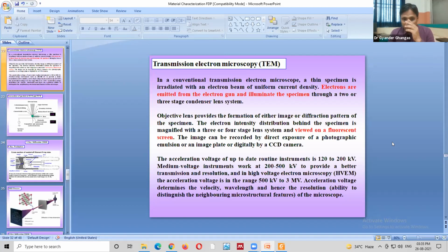So the acceleration voltage of a routine instrument up to date is 120 to 200 kilovolt, and medium range 200 to 500 kilovolt, to provide better transmission and resolution. And in a high voltage electron microscope, it will range up to 500 kilovolt to 3 megavolt. The acceleration voltage determines the velocity, wavelength, and hence the resolution of the microscope.